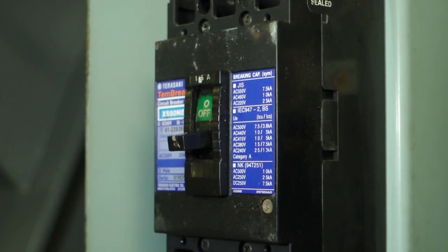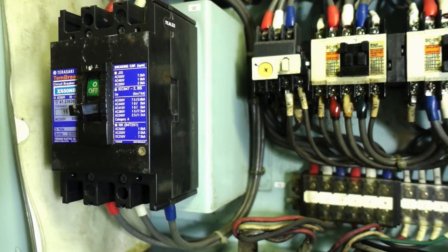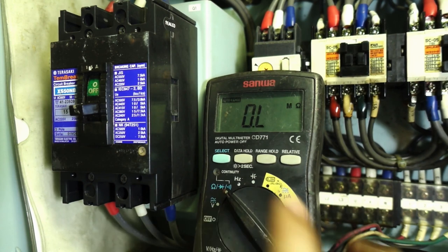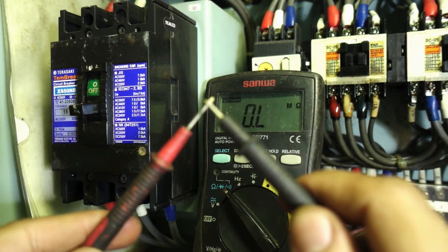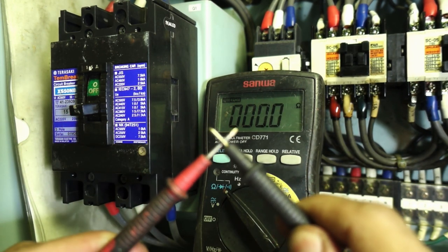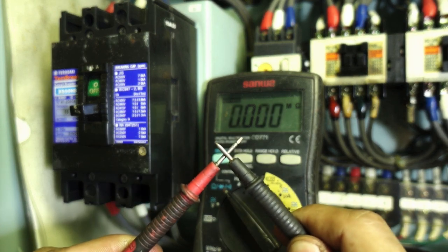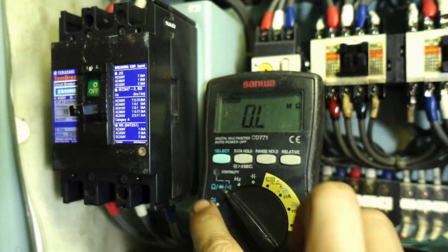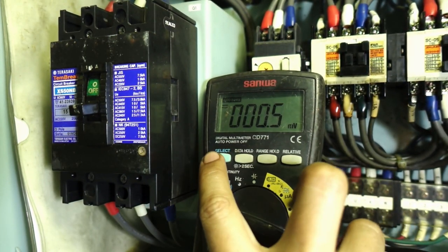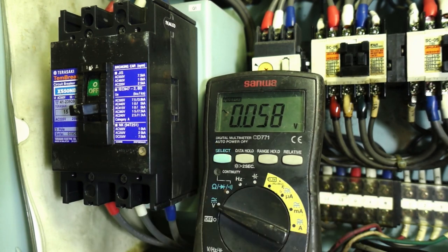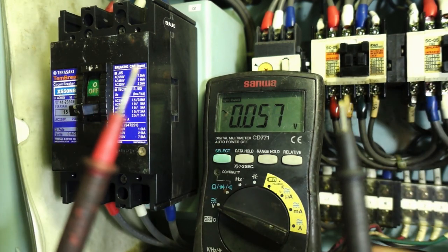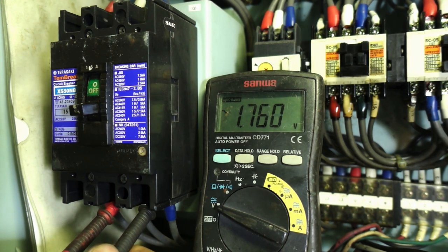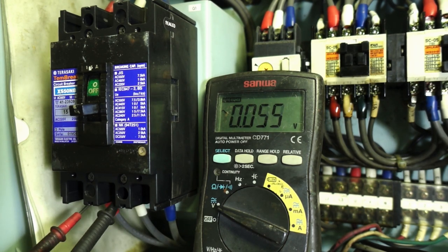I switch off the circuit breaker and I would put a lockout tagout if available. I test my tester to ohmmeter to check continuity in between leads. I switch to voltmeter and check if there's no more voltage in the circuit. The reason I did this is because I don't want to be electrocuted during the process.